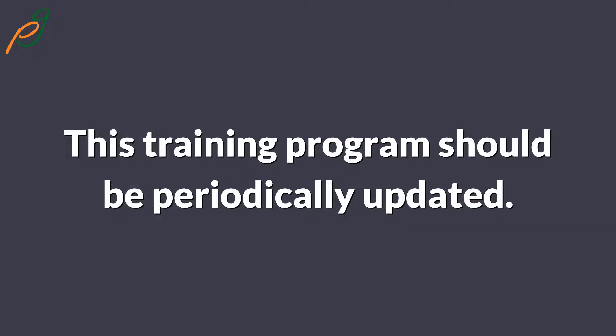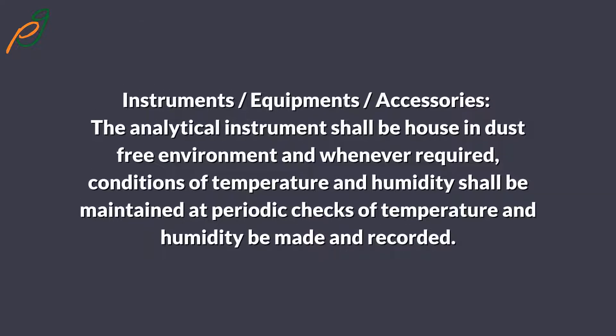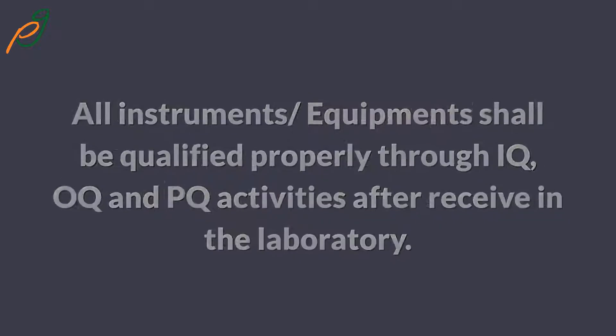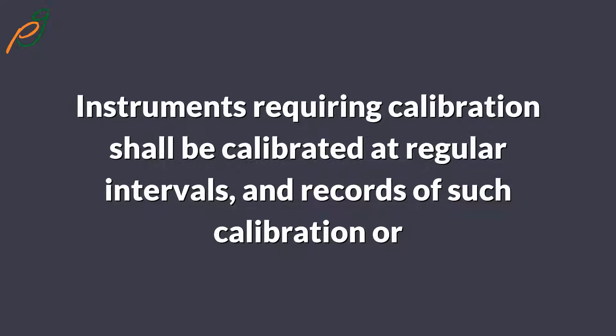Analytical instruments shall be housed in a dust-free environment and, wherever required, conditions of temperature and humidity shall be maintained. Periodic checks of temperature and humidity should be made and recorded. All instruments and equipment shall be properly qualified through IQ, OQ, and PQ activities after being received in the laboratory.